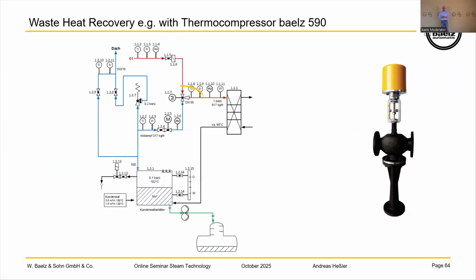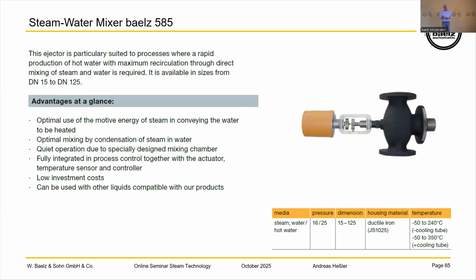Thermocompressors. The next one, where hammering is also a good issue. With our steam water mixer we want to heat up water, to spray or to put into steam. There we have a special valve. For example, you have 5-bar steam at 180 degrees, and water at 20 degrees and 2 bars, and you want to heat it up to about 60 degrees. You can put the steam right inside the water to heat it up, so you need no heat exchanger. But this is very critical, and this valve is very special.